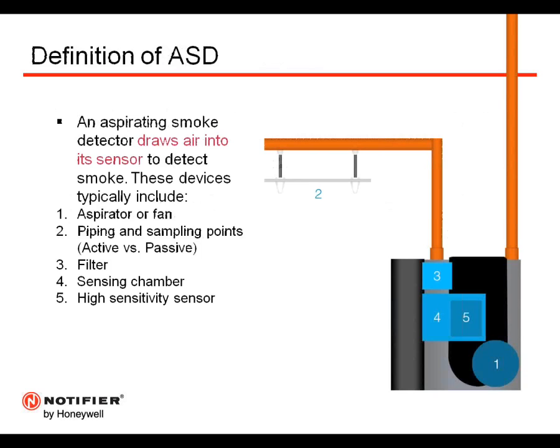So how aspirating smoke detection works: they have a fan or an aspirator inside the housing of the detector itself, and they run a pipe network out into the area being protected. These pipe networks have sampling ports, and each sample port is equal to a spot type detector in terms of spacing. All aspirating detectors incorporate some sort of filtration technology in order to remove nuisance particulate from the sample, and then a high sensitivity sensing chamber, which allows very early warning smoke detection per NFPA 76.